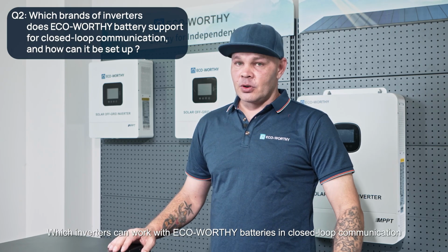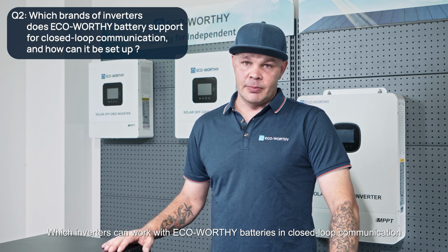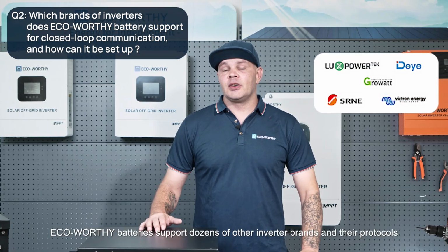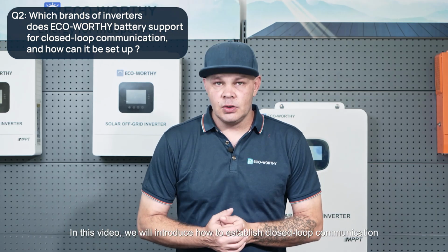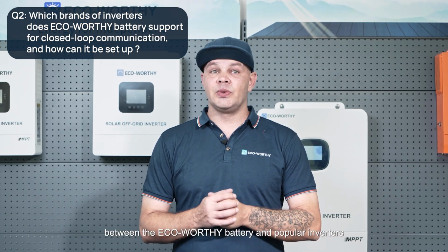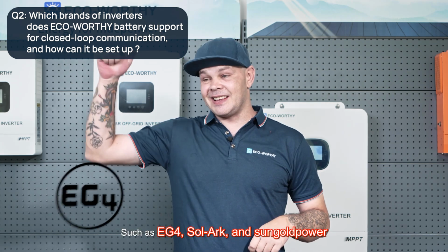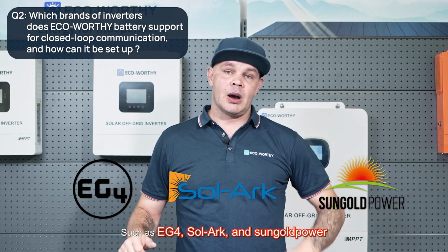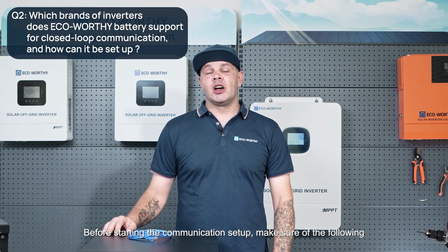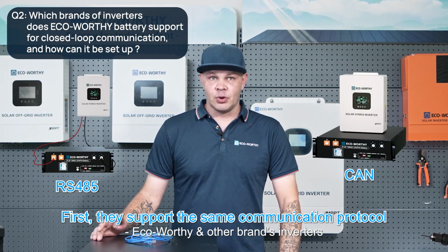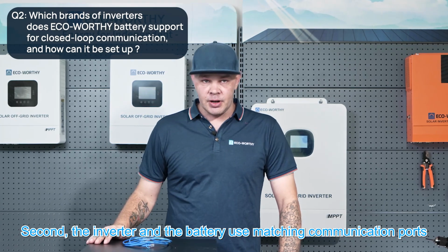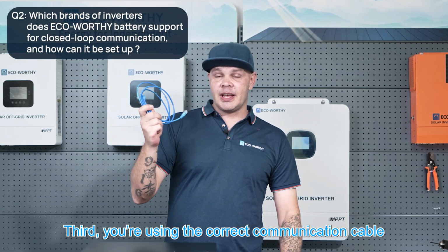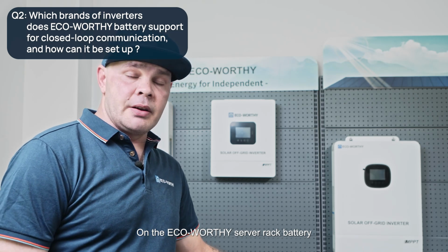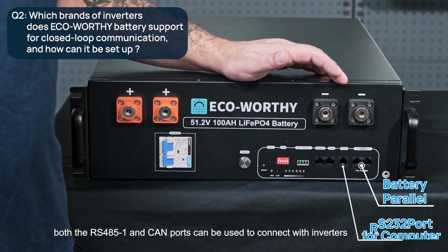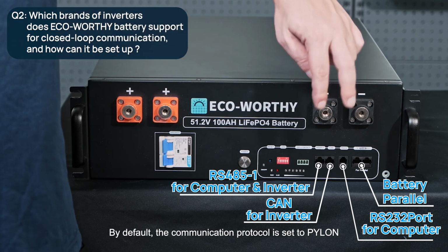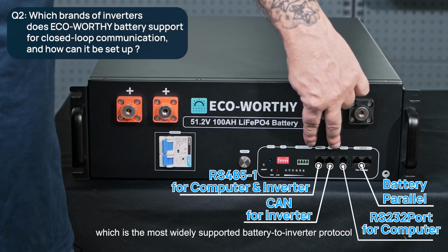Many customers wonder which inverters can work with eco-worthy batteries in closed-loop communication. Eco-worthy batteries support dozens of other inverter brands and their protocols. In this video, we'll introduce how to establish closed-loop communication between the eco-worthy battery and popular inverters such as the EG4, SolArk, and SunGold Power. Before starting the communication setup, make sure of the following. First, they support the same communication protocol. Second, the inverter and the battery use matching communication ports. Third, you're using the correct communication cable. On the eco-worthy server rack battery, both the RS-485 and the CAN ports can be used to connect with the inverter. By default, the communication protocol is set to Pylon, which is the most widely supported battery-to-inverter protocol.